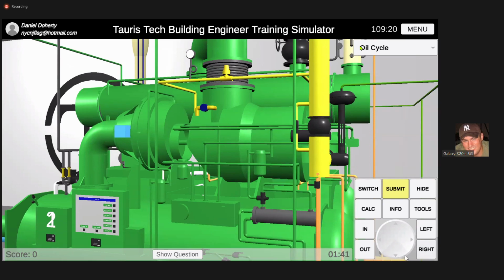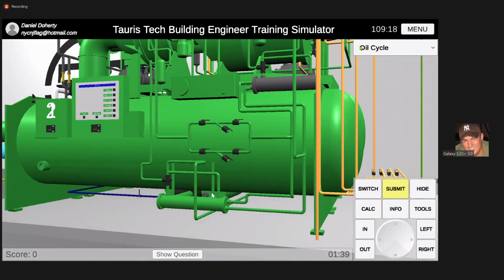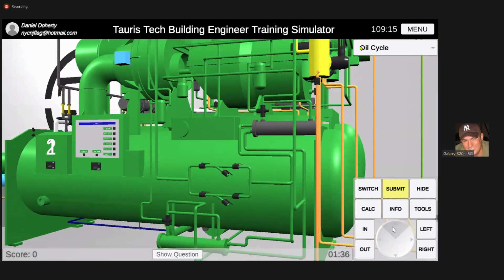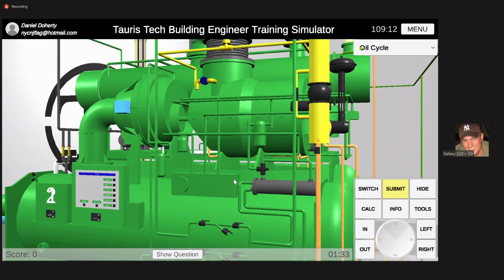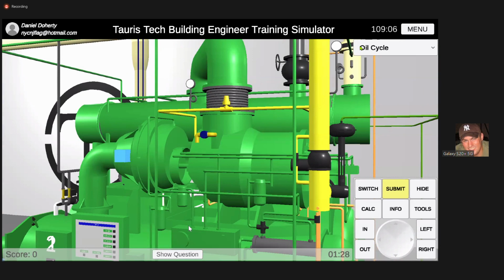Hey, wait. The sump down there, that's your compressor oil sump. And then this box right here is your turbine oil sump. So if I remember correctly, it gets pulled through your auxiliary oil pump. This comes around, it goes down, and goes to your thermal valve. And then the thermal valve works the same way down there. If it's too hot, it's going to go this way and go to your heat exchanger. If it's not too hot, it's just going to go this way. It's going to go through your filter for the turbine.